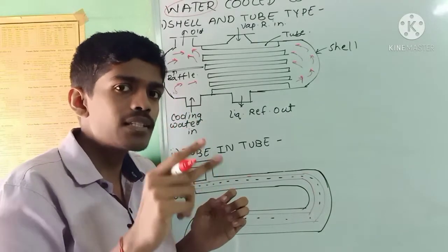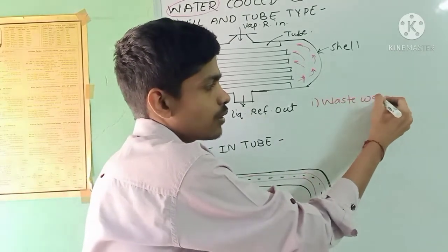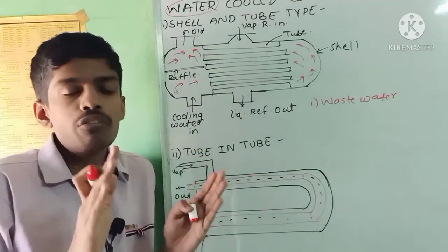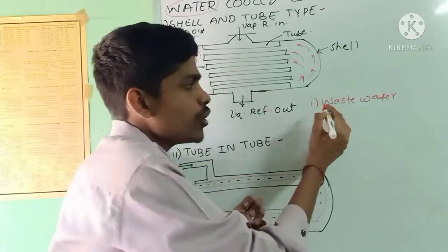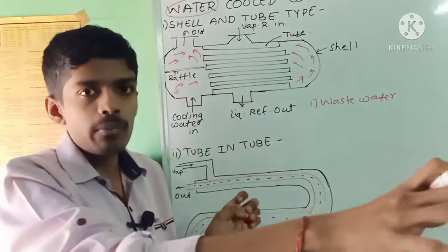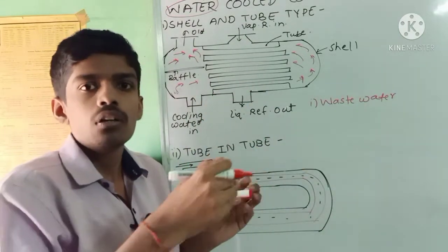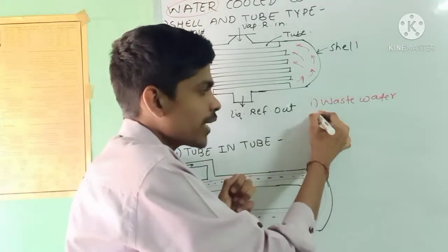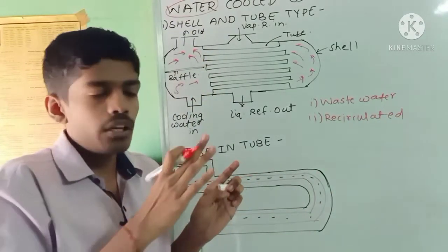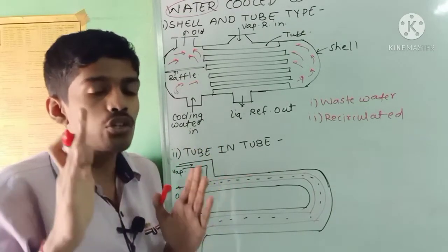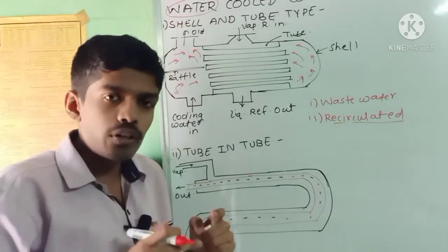There are two systems by which we can send water to the condenser. The first is the waste water system — if a plant is located where plenty of water is available, water from the city main is sent to the condenser and after use is discharged to a river or sewage. The second is the recirculated water system — used where water is scarce, in which the water sent to the condenser is reused after use.